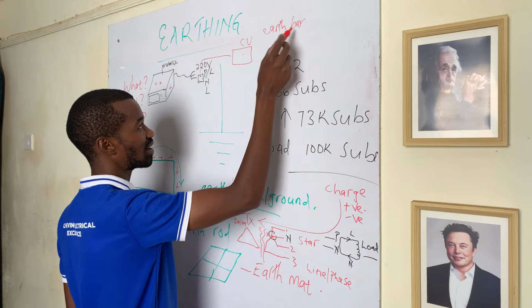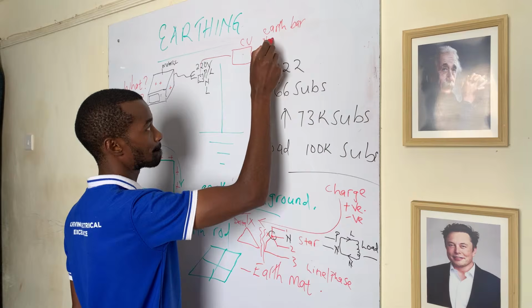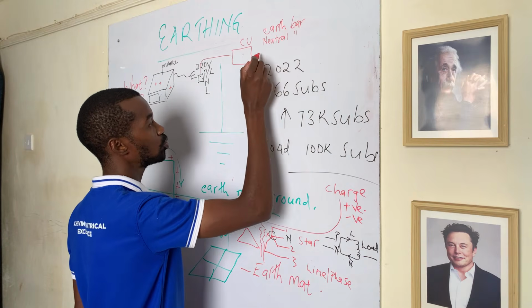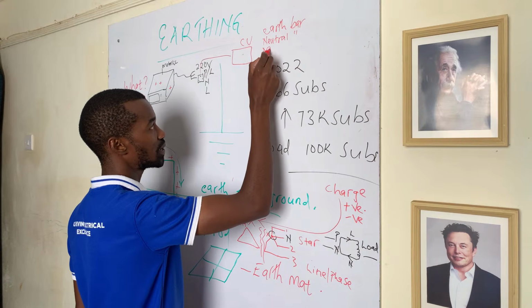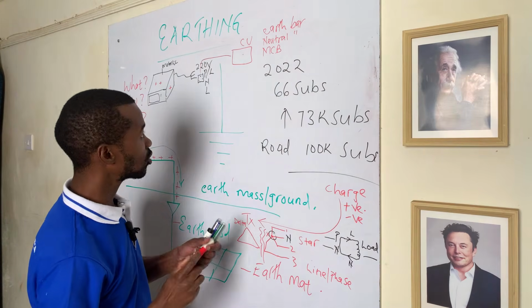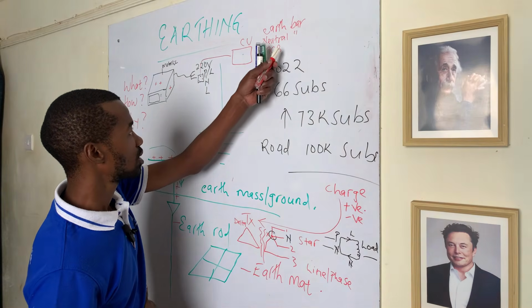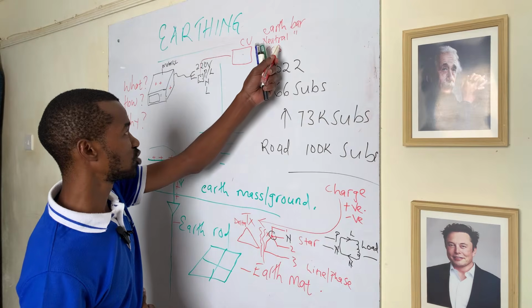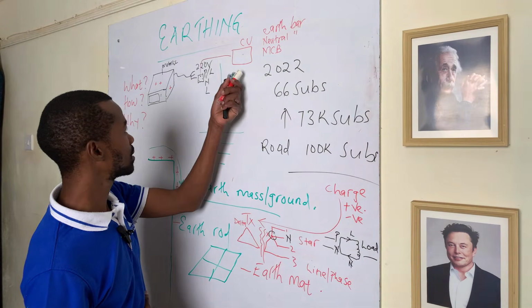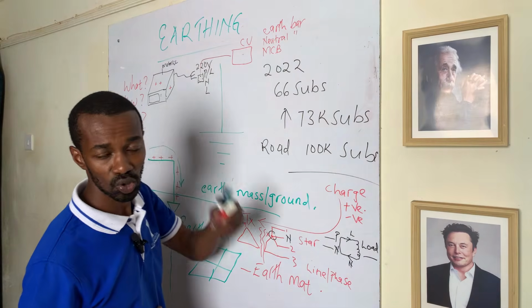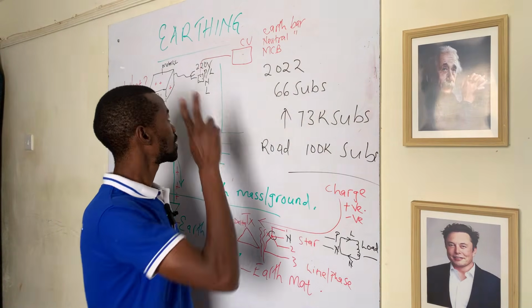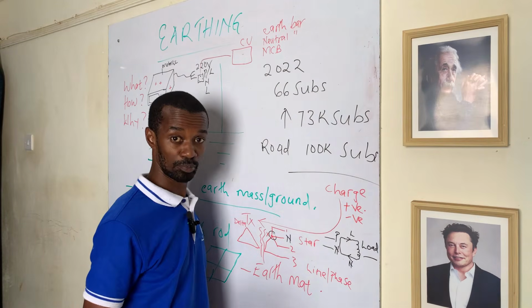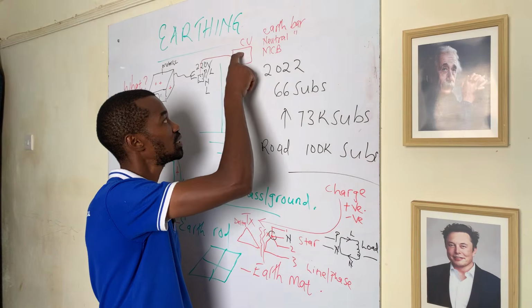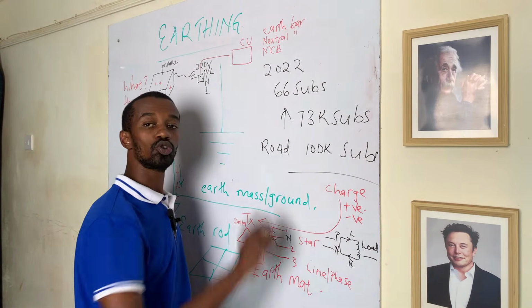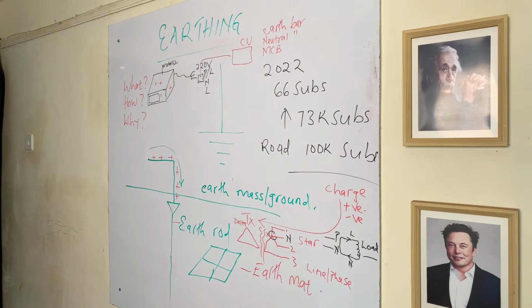I mean, at the consumer unit, we'll have the earth bar, we'll have the neutral bar, and we'll also have the MCB. So as much as we are connecting the line and the neutral to the MCB, as well as to the neutral bar respectively, the earthing has to be continuing all the way from the sockets. So this is where the wiring comes in handy. The wiring from the sockets, from the lighting points, all the lighting points have to be in contact with the earth bar in the consumer unit. That one you have to check properly.